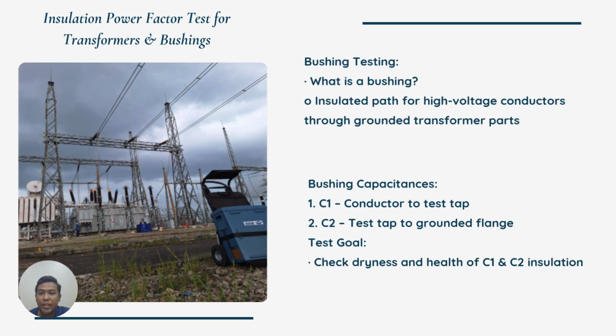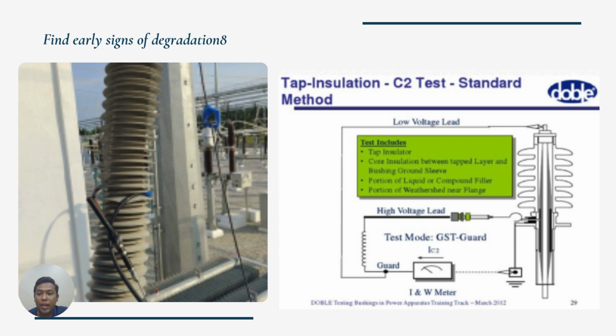Let's talk about bushing power factor testing. A bushing is the part that lets high voltage wires safely pass through grounded equipment like transformers. It needs to withstand both electrical stress and mechanical force. Inside the bushings, we measure two key capacitances. C1 is between the main conductor and the test tap, and C2 is between the test tap and the grounded flange. We do this test to check the condition of the oil insulation inside. A high power factor tells us if there is moisture contamination or deterioration. The goal is to catch problems early and keep the bushing working safely. That way, we avoid unplanned failures and keep the system reliable.